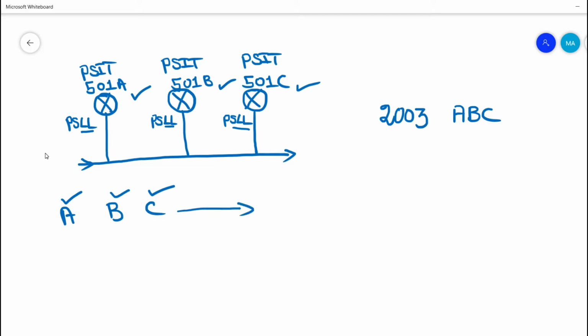These transmitters will get into 2 out of 3 voting. So the ESD algorithm will not wait for the third transmitter. If any 2 transmitters win the logic, that is, if any 2 transmitters sense low pressure, immediately an ESD trip action will occur. This is in ideal condition.